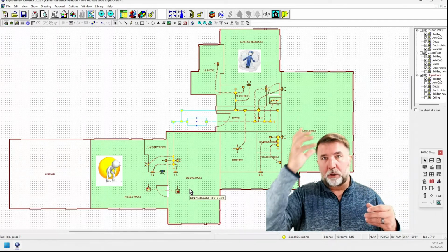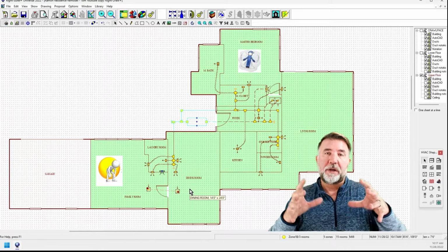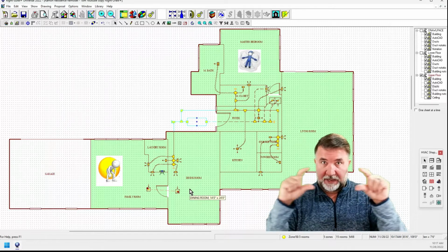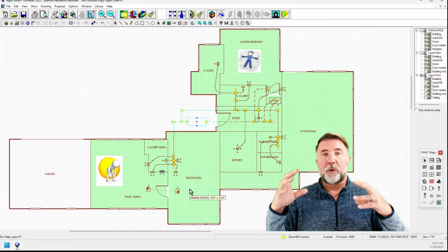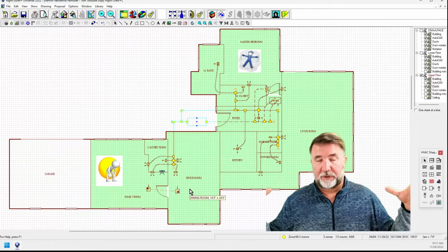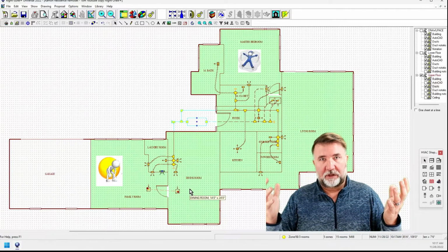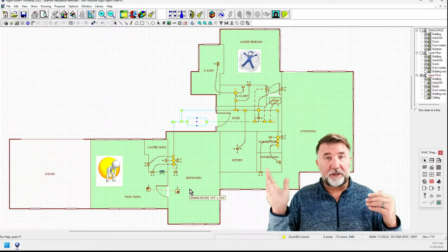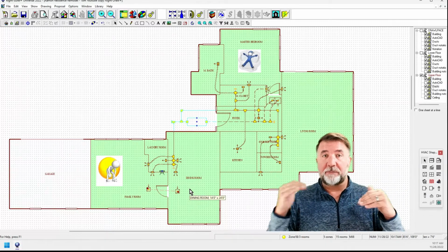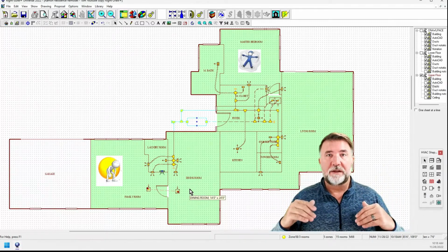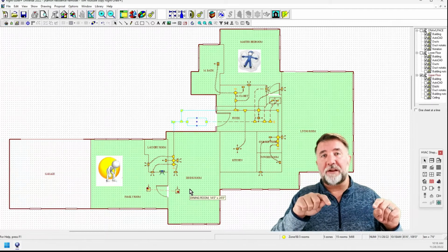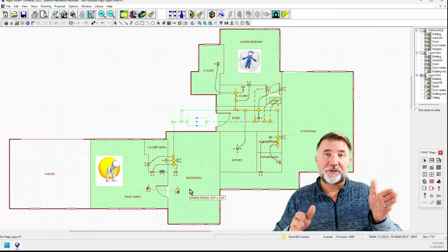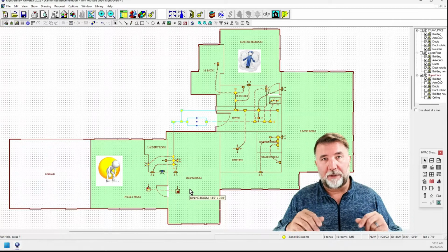Because it's only working off of pressure. So we push the air into the room, but we've made a larger area for the air to be forced out, again just like the undercut door. There's no guidance on how much. You can make the duct bigger or smaller, but the duct is going to take what it wants to take at that point in time based on outside pressures, temperatures, and things like that. And at different times in the day, that's going to fluctuate. So the only benefit of this, which is the next, I guess I put the transfer grill as the least attractive. This is the middle, and then we'll talk about the direct one in a second.